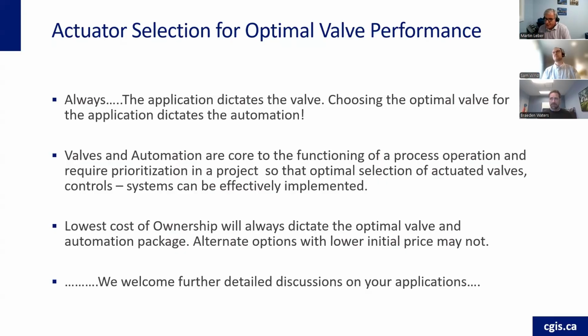But also a big consideration is the valve you're putting it on. Some valves, wedge gates for example, really should be up and down every time — the packing design isn't ideal for the side load of a heavy actuator off to the side. Other valves, like the DSS knife gate valve with the heavy top works, have a lot more flexibility for installation in different orientations. It's a great question and something we should be asking and working through when specifying those actuators.